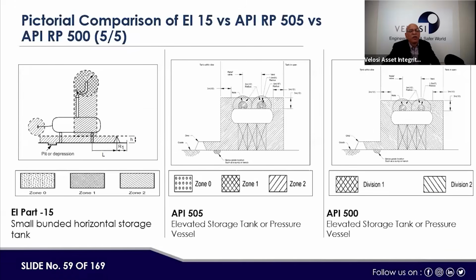So this is another example, where for a small bunded horizontal storage, we can see how the classification is shown. This is the legend or the guideline. Zone 0, zone 1, zone 2, always remember. Zone 0, zone 1, zone 2, then division 1 and division 2, as per EI part 15, API 505, then API 500. These pictorial pictures are available in these standards, and they help us show where, like here, this one is zone 2, and this is the vent of the PSV, where up to 2 meter zone 1 is considered. Same is here, mostly zone 2, and then some area as zone 1. Here, everything is division 2, and some areas are division 1.